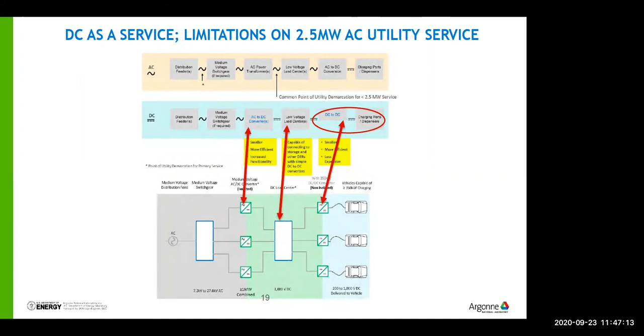It's a pilot. We have our distribution feeder going to medium voltage. That medium voltage goes directly to DC, cutting out a bunch of steps and equipment, called a solid state transformer. To the right of that, we have low voltage distribution centers, which we'll talk a lot about in coming slides, then the DC to DC converters, the dispensers, and then the charge ports and electronics. This cuts out steps and makes it scalable. At that first red arrow in the middle, I can keep adding more source to the left and more distribution to the right. There are diminishing returns, I can't put 1,000 trucks on one feed, but I can put tens or hundreds on one feed.